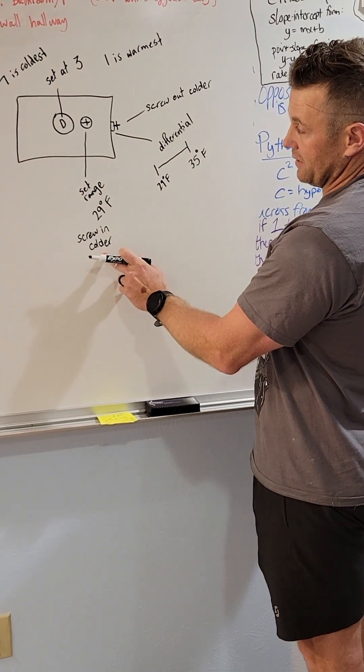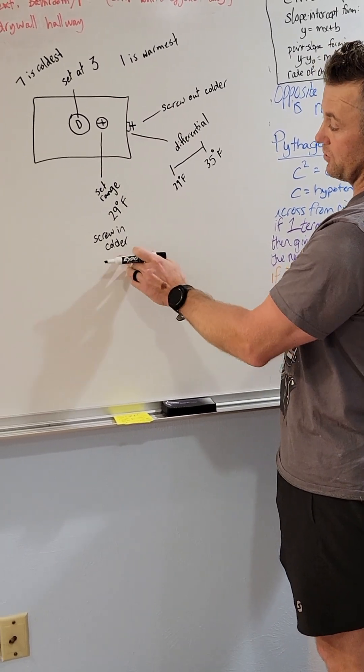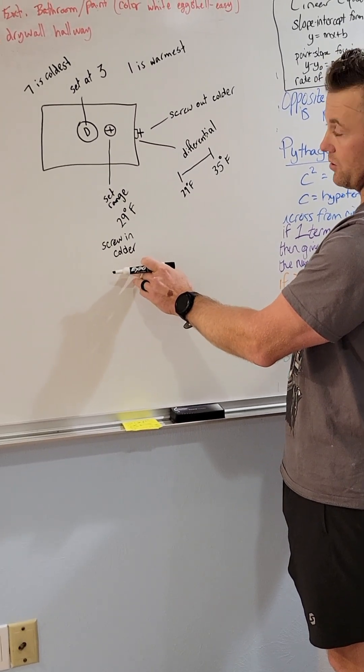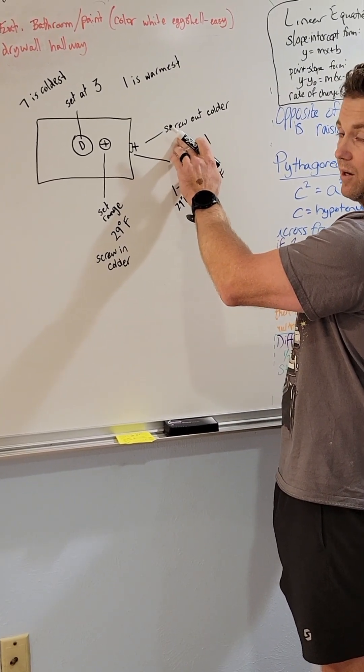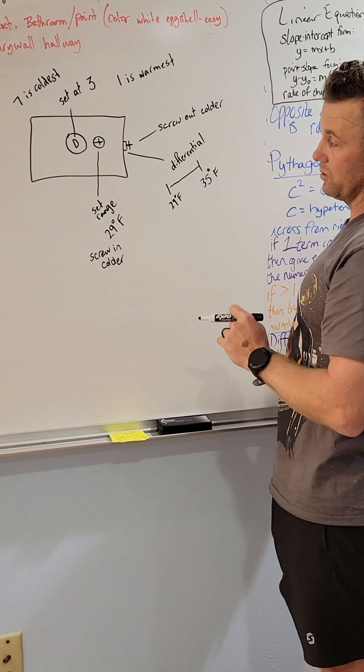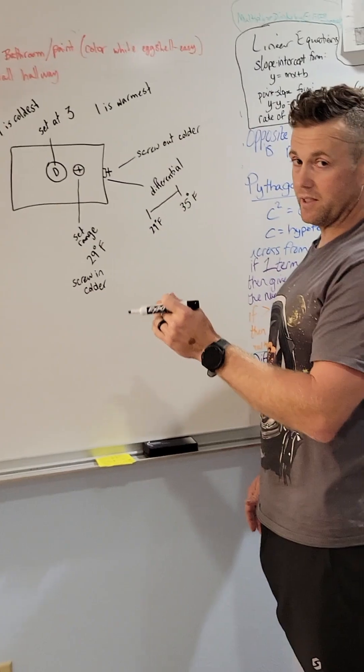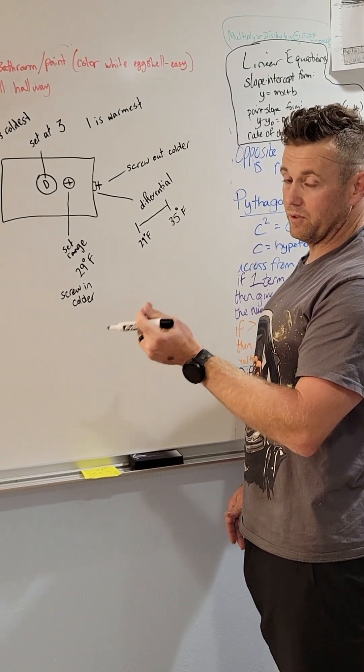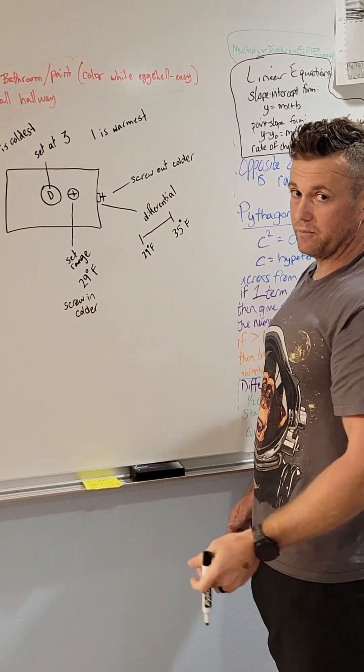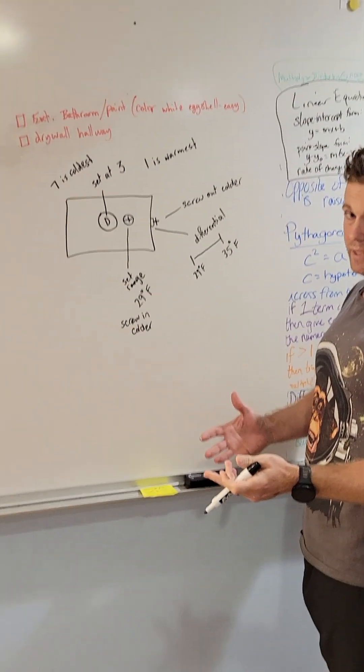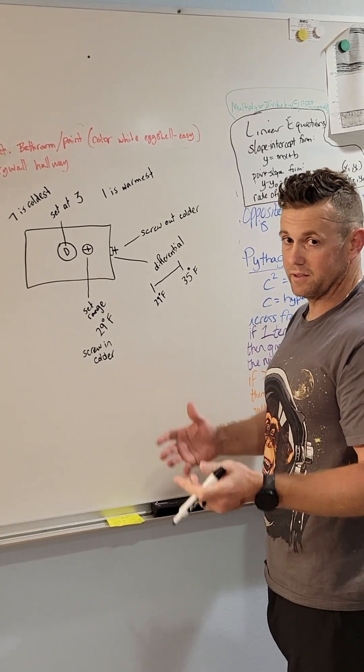So when you screw this in, this makes it colder. So screwing it in clockwise makes it colder. And on the differential, screwing it out or counterclockwise makes it colder. Different variations have different ways they operate. You've got to kind of play with that if you don't have a spec sheet or any way of knowing that. But I thought this would be helpful. It's been tremendously helpful for me on understanding thermostats better for refrigeration. Hopefully it does you too.